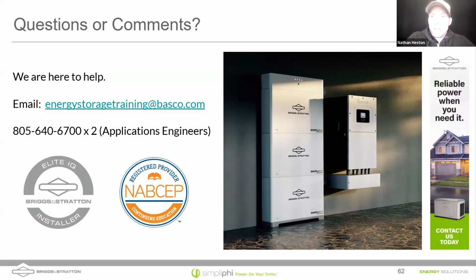So unfortunately, that is correct, that the Tigo transmitters will use power in order to keep the solar alive. So it's one of those unfortunate consequences of the rapid shutdown rule, right? Is that your solar sometimes will not start back up after a shutdown event. So there are different things you can do. For one, you could power the rapid shutdown transmitter of the Tigo directly from the DC power of the batteries. And so that's what I've recommended to installers is to get a 48 volt to, I believe some of the Tigo transmitters will take 24 volts. So you could get a power supply that'll pull DC to DC. Or you could get a battery backup for your Tigo transmitter, which seems ridiculous. But yes, that is an unfortunate consequence of using the Tigo rapid shutdown devices.